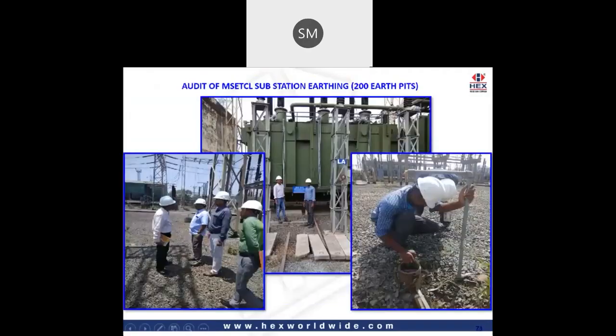We also conducted an audit for the MSETCL substation earthing, where there were 200 earth pits. We went and measured each and every earth pit, the grid. We gave our report. Now we are in the process of implementing the solutions that we have given them. And they in turn have rewarded us by asking us to audit another 27 substations.